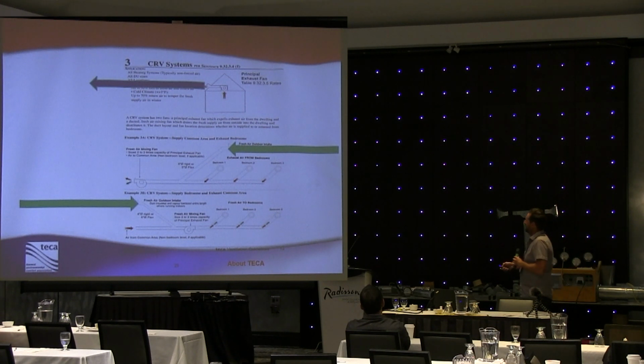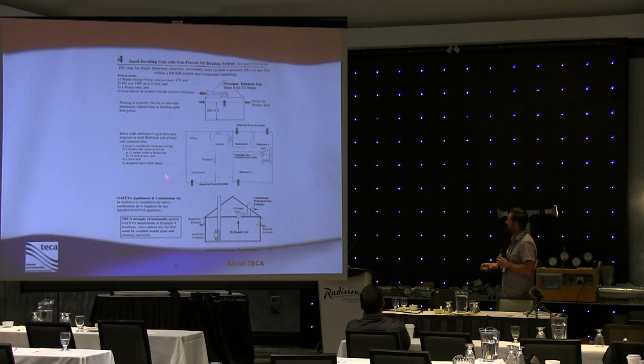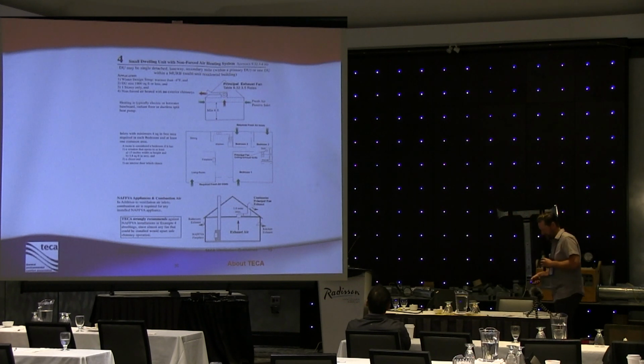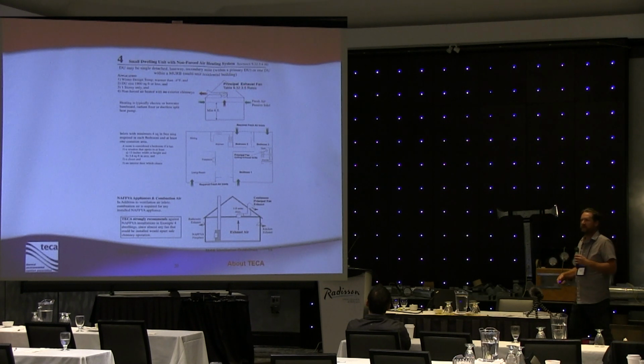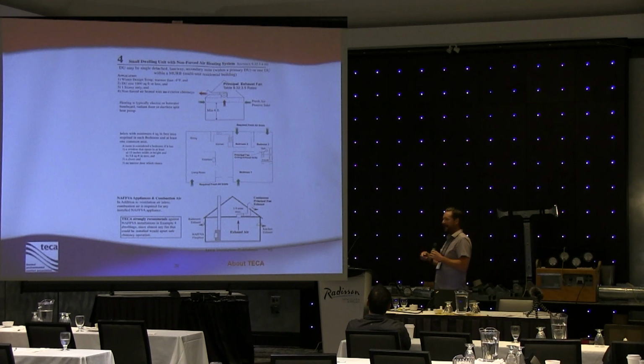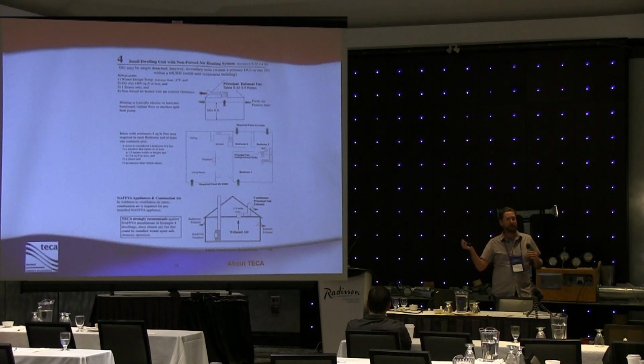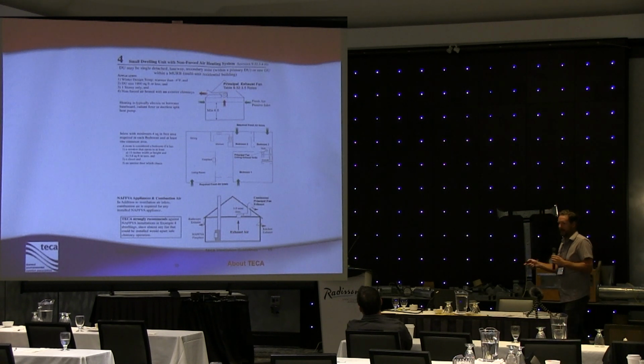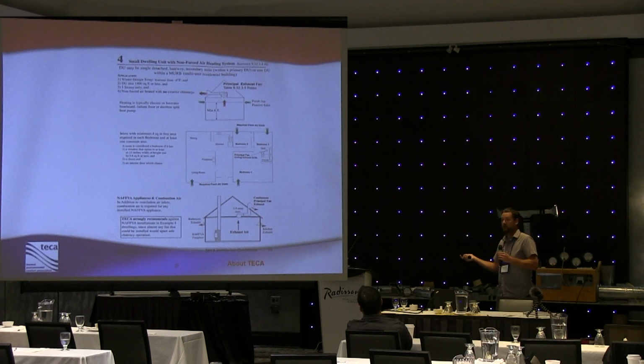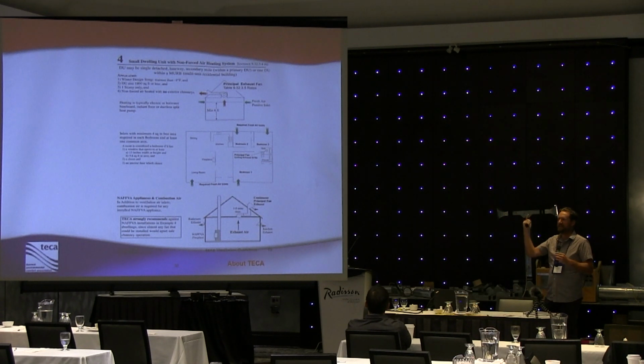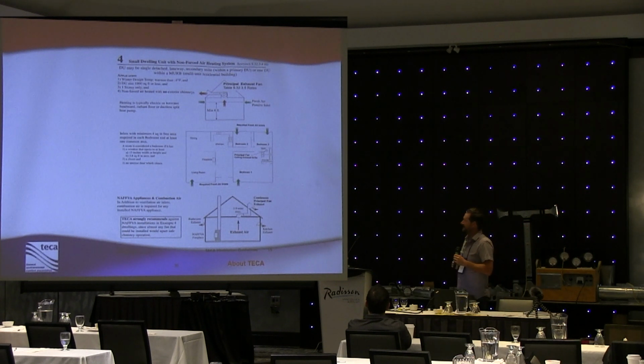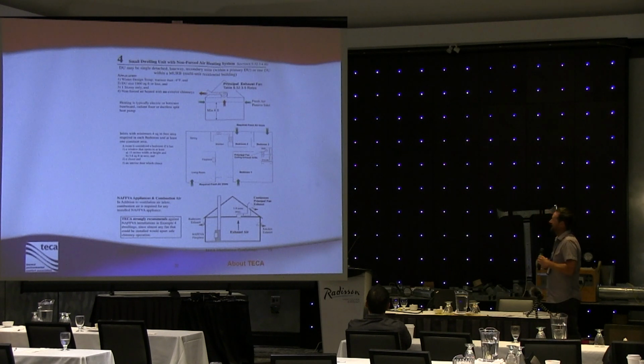Okay, good. Good deal. These small dwelling unit systems like this, again, what was I going to touch on with these? There is, with any type of ventilation system that we use that is taking advantage of a principal exhaust fan, these principal exhaust fans, I keep saying that they should be installed in a bathroom. They don't absolutely have to be installed in a bathroom, but it makes the best fit. You're putting a bathroom fan in anyways, so why wouldn't you use one of those fans to be your principal ventilator? Well, with this principal ventilation fan, a couple of things you have to keep in mind. One, we want it to be energy efficient. We want to put in a good fan. The other thing is we have to make sure that fan is not too noisy, right? There is a code requirement that that fan cannot exceed 1 sone of noise allowance. It can't exceed 1 sone. Sone's a measurement of sound, and if it exceeds 1 zone, it's not acceptable. It's not an acceptable fan to use as your principal exhaust fan.